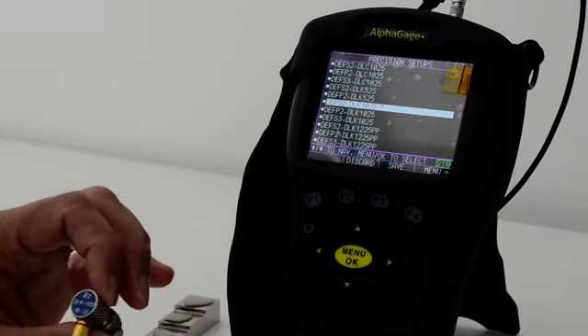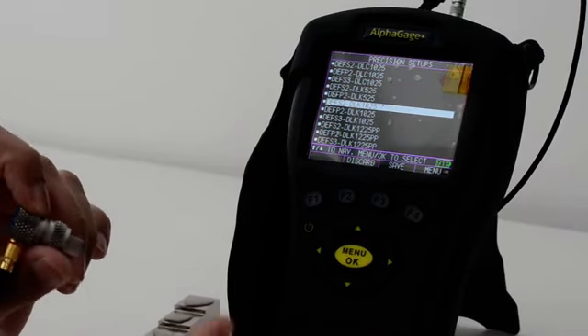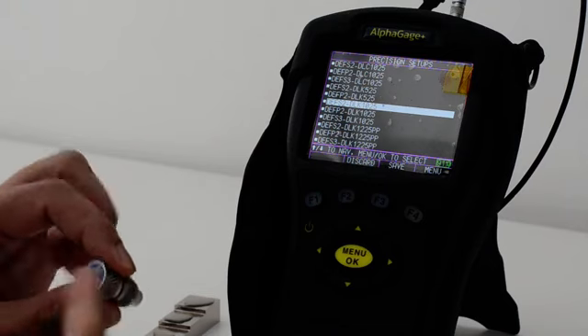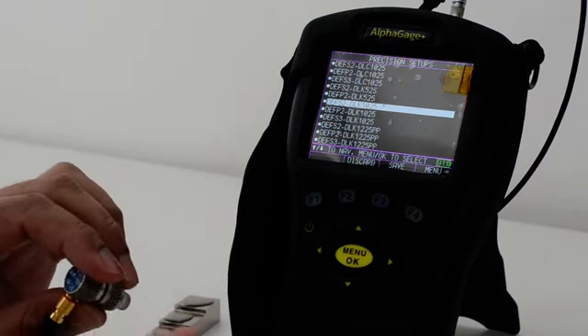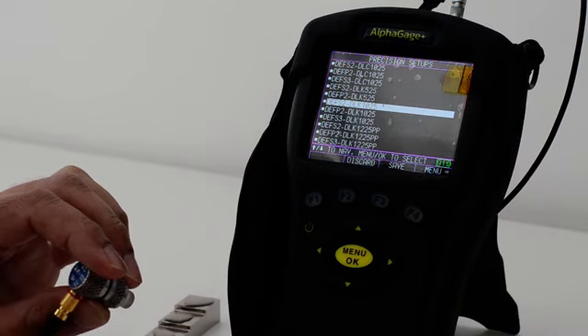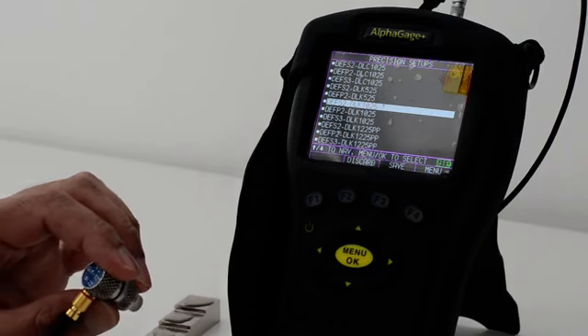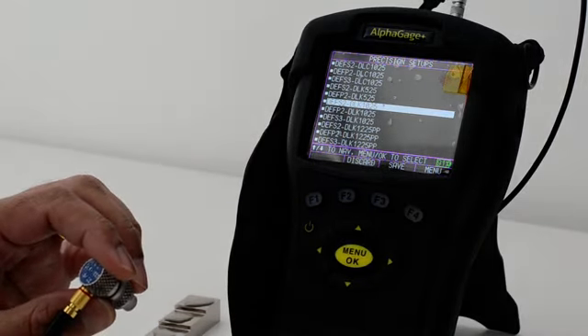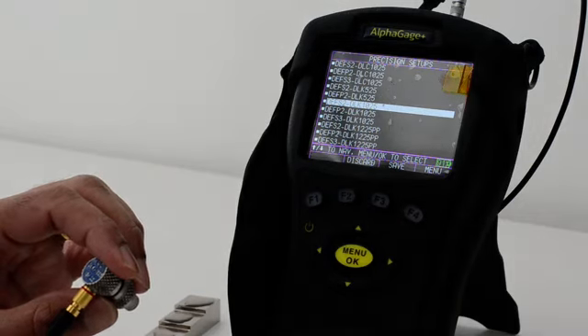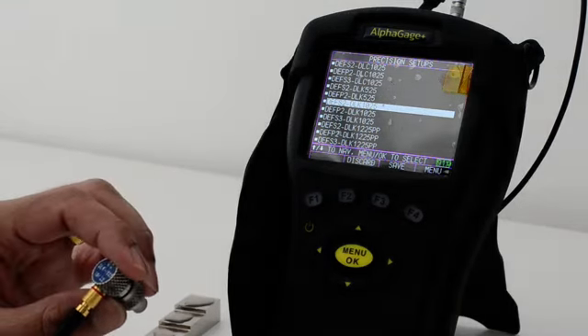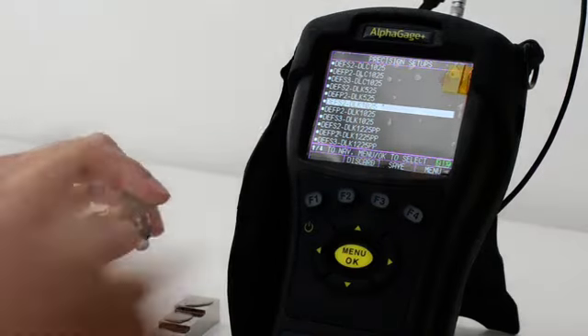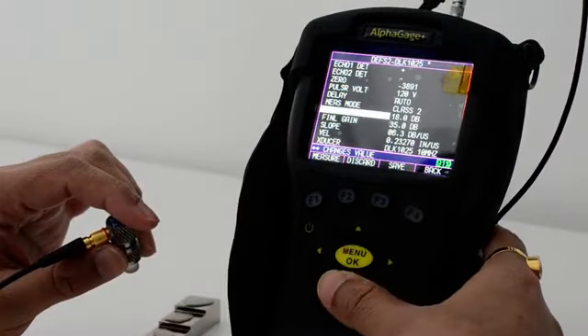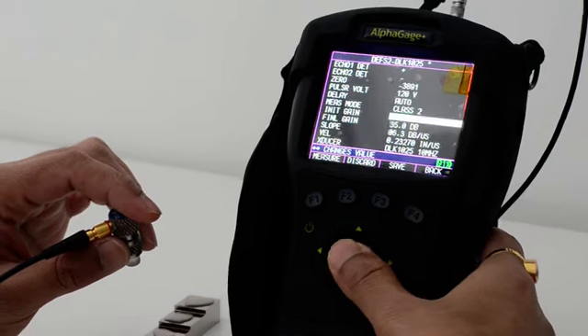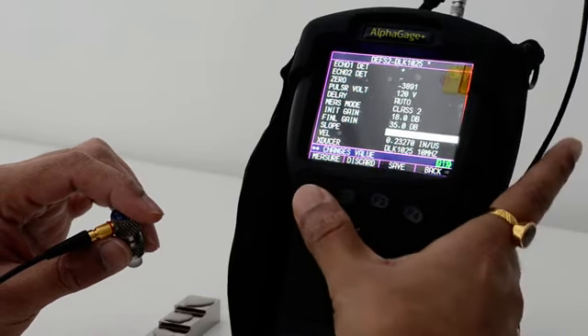Class 2 measures from the interface echo to the first back wall, and class 3 is defined by measuring the two back walls. So it depends on what you need based on the accuracy. If you go for class 3, then it is higher accuracy, but it requires higher power, or it is better to do it in thinner materials. So let's start with the class 2 one. You have to press OK and then again press OK and then press measure.